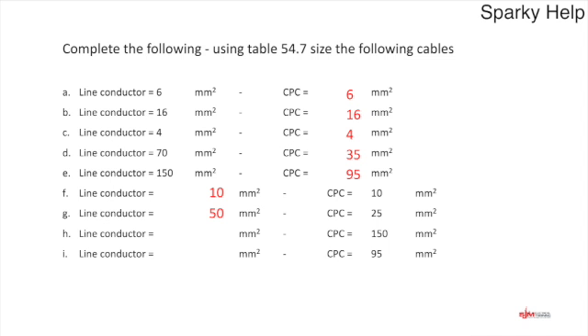If you had a 150 earth, then double that. They do make a 300 mil. And a 95, well, that's similar to the one above, so you would end up with a 150. So that's a very quick, easy way. And if we do this and we size our earths according to table 54.7 of BS 7671, you will always get it right. It may not be the smallest you could have got away with, but it will work.